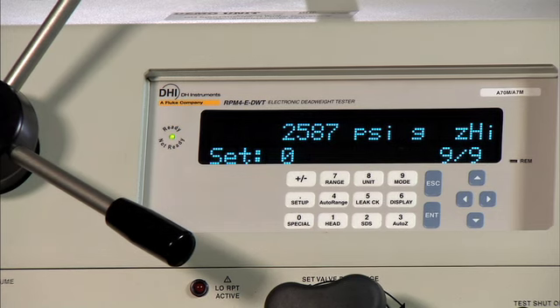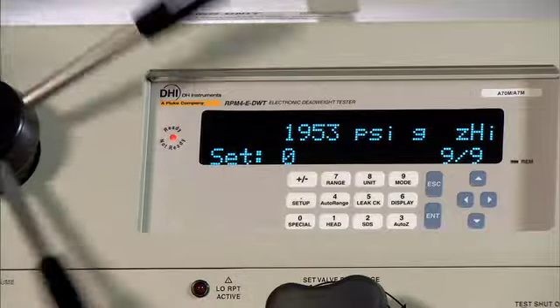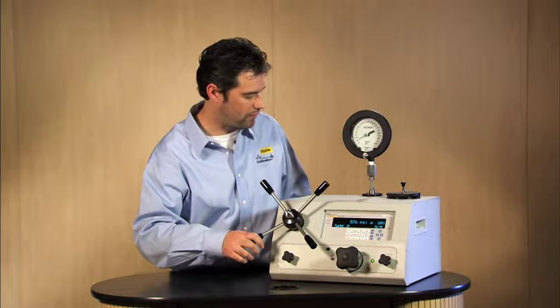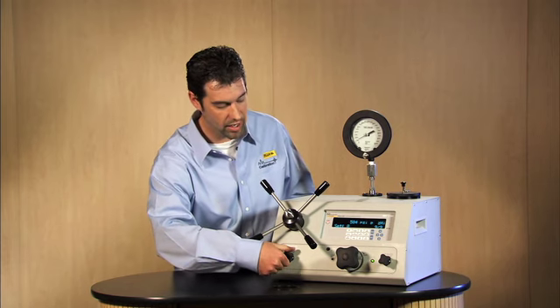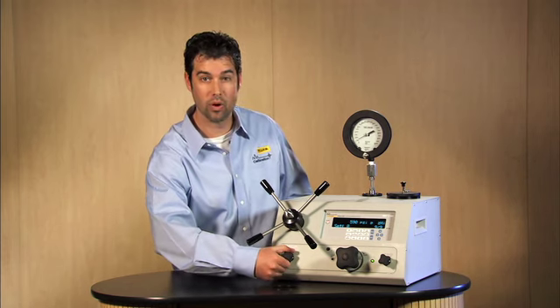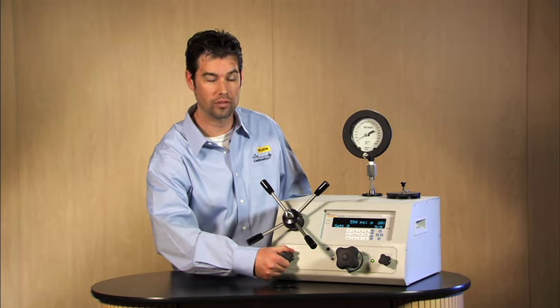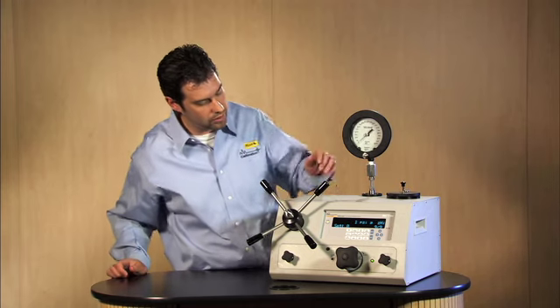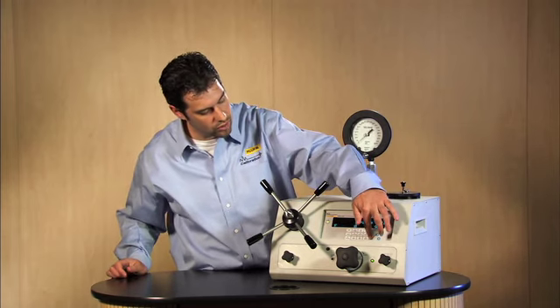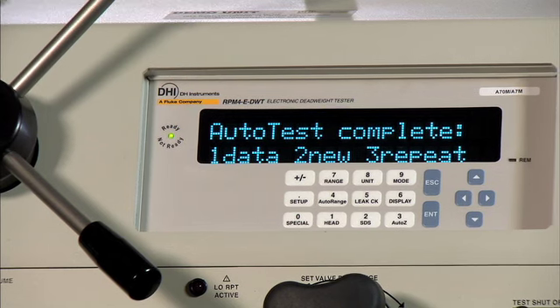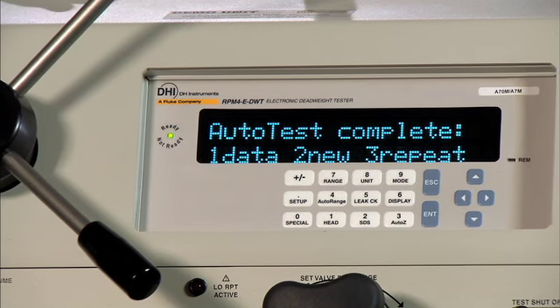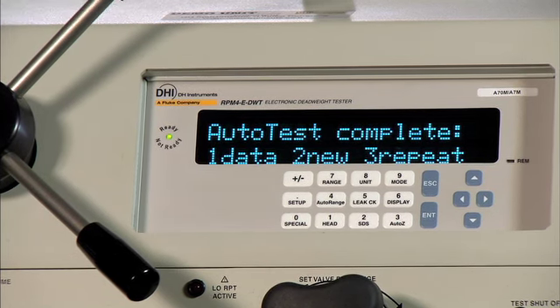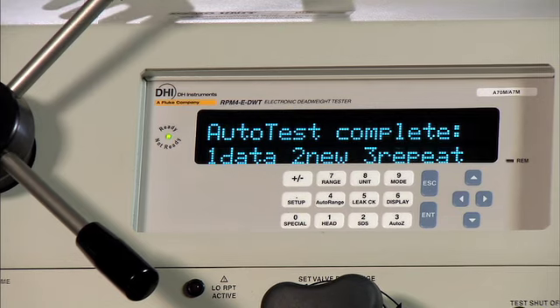To set zero pressure, I recommend reducing it to about, I don't know, 100 psi or 500 psi. And go ahead and open up the reservoir isolation valve. See if we're ready. We are ready. Push enter to acknowledge it. Now it gives you a menu structure that we can decide to rerun the test, to do a new test, to look at the data. And that's how simple it is.